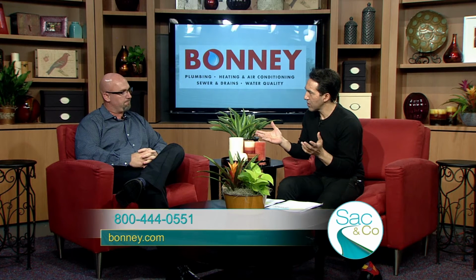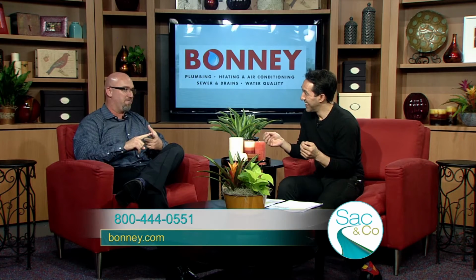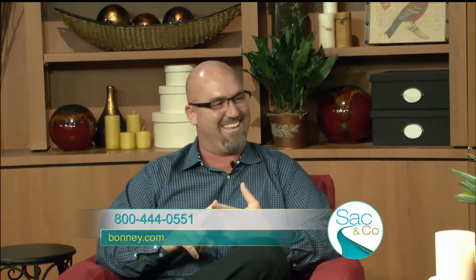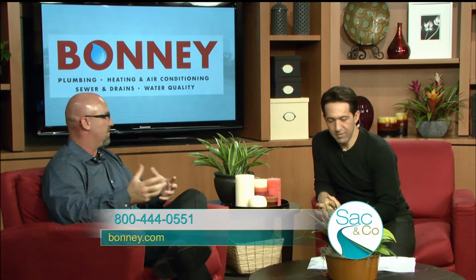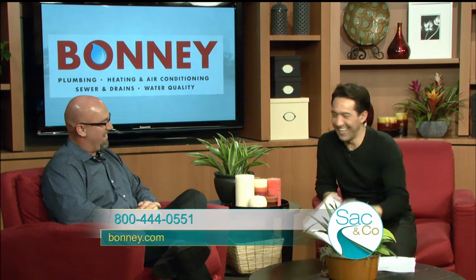So what about hot water? Why do we run out of hot water so quickly? Quickly depends on you. If you're taking a 45-minute shower, that's not quick. Is that a long shower? But typically it's going to be something going on with your water heater. The bottom of it can be full of mineral. There can be several issues going on with it, but if you're running out real quick, there's definitely an issue there. Could be one of the elements, if it's an electric, has gone bad. Could be multiple things. All right. Note to self: 45-minute shower too long. That's right.